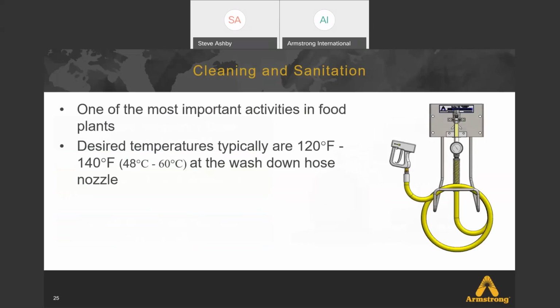So the cleaning and sanitation, again, is what's most frequently addressed with direct contact heating. Most of the temperatures we see are in 120 to 140 range. That sometimes goes a bit higher than that, but more times than not, that's the temperature range that customers are looking for. Typically, we hear a plus or minus 5 degrees. If that's the case, just a very simple single temperature type hose station can address this. No mixing valve necessarily required, just an on-off ball valve, then with it feeding your hose and your nozzle.